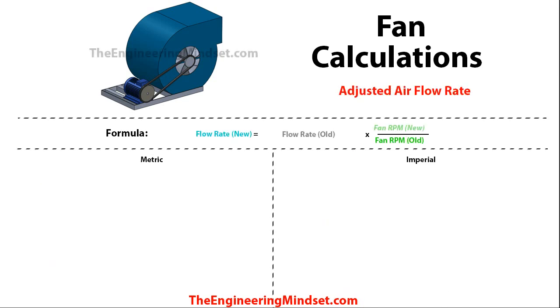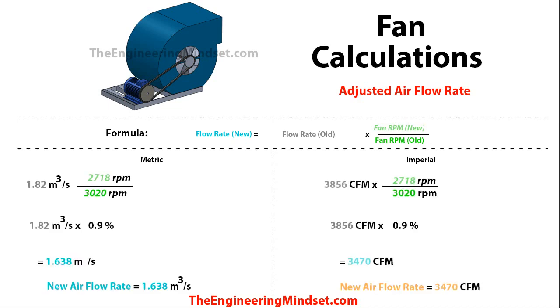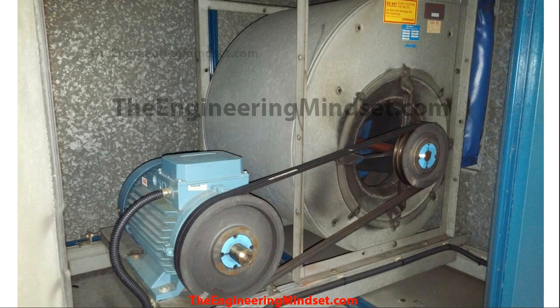If you've made changes to the fans and motors, you'll want to know the adjusted airflow rate and whether it satisfies the design criteria or achieves energy savings. The formula is: new airflow rate = old airflow rate × (new fan RPM ÷ old fan RPM). Plugging in the figures — the RPMs form a ratio — and multiplying out gives 1.638 m³/s (3470 cubic feet per minute).